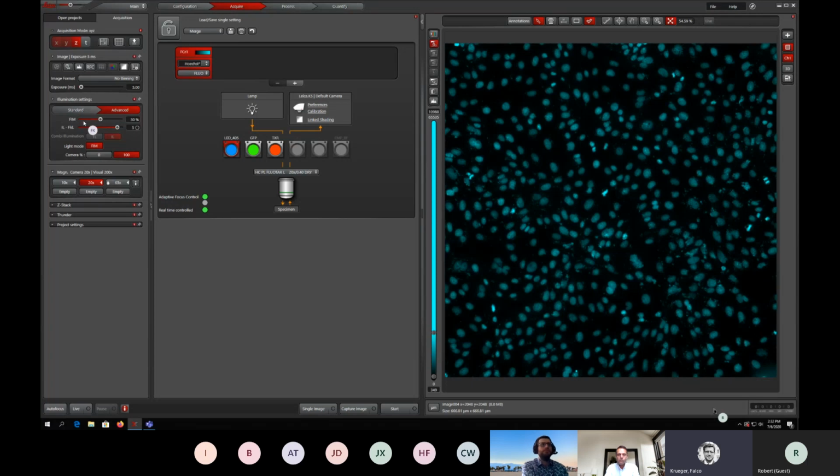Okay, so we talked about the illumination settings, where you can control with the so-called fluorescence intensity manager the amount of light that is being put onto your sample. Then there's another advanced control that you have, the ILFD. What does it mean? Incident light field diaphragm. This is the shape with which the sample is being illuminated. Let me demonstrate this. Right now we have size 5, a circular structure.